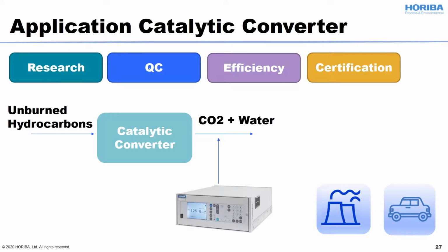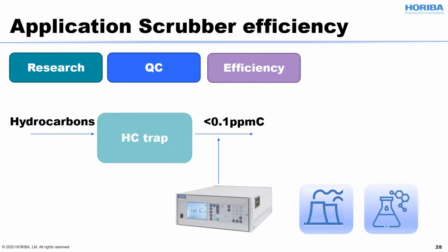For the users in the plant, a steam boiler for the oil refinery would be another application. Emissions from fuel such as diesel, oil, gasoline, and others produce many more heavier hydrocarbons in the exhaust emission compared to compressed natural gas emissions. So it is important that the catalyst works properly to convert those hydrocarbons. Since those fuels contain heavy hydrocarbons in the exhaust emission, all of the measurement line needs to be heated above 191 degrees C. A hydrocarbon trap is similar to the catalytic converter. A hydrocarbon trap captures the slip hydrocarbons. For the quality check, you measure in and out of total hydrocarbons so that you can ensure the trap is working well.